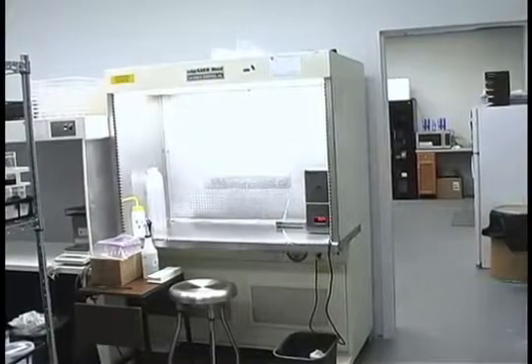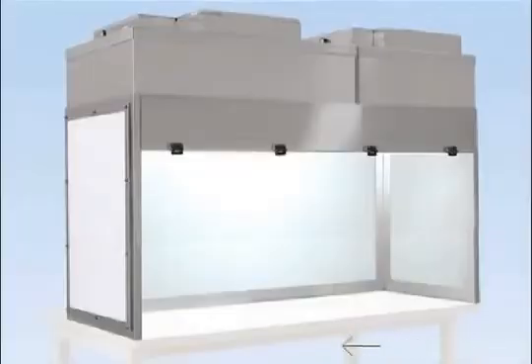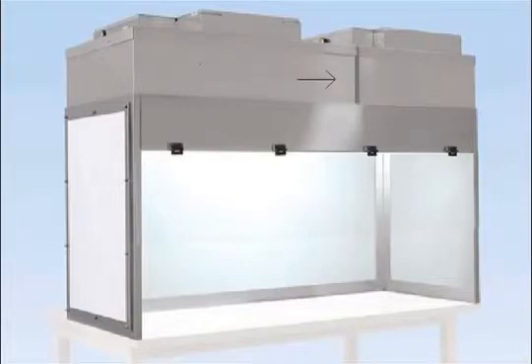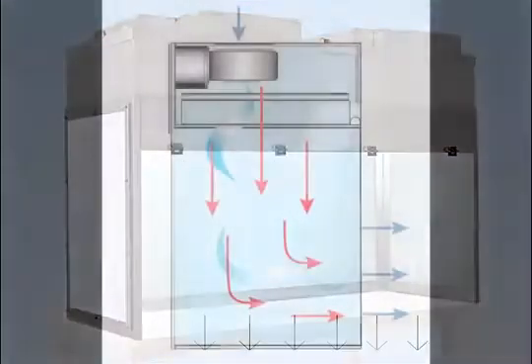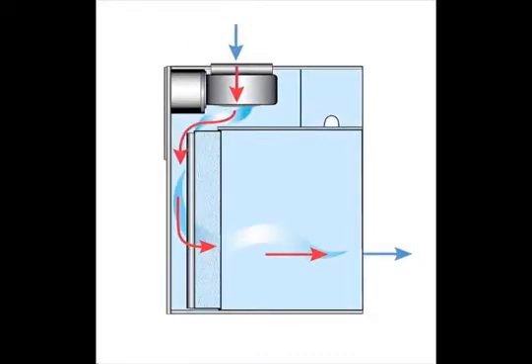A horizontal laminar flow unit is designed to remove the particles from the air. Room air is pulled into the top or bottom of the unit and pushed through a high efficiency particulate air, or HEPA filter, with a uniform velocity of 90 feet per minute across the work surface. The air is filtered by the HEPA filter so nothing larger than 0.3 micrometers can pass through, rendering the air sterile. The flow of air from the unit prevents fungal spores or bacteria from entering. All items going inside the unit should be sterile or sprayed with alcohol.